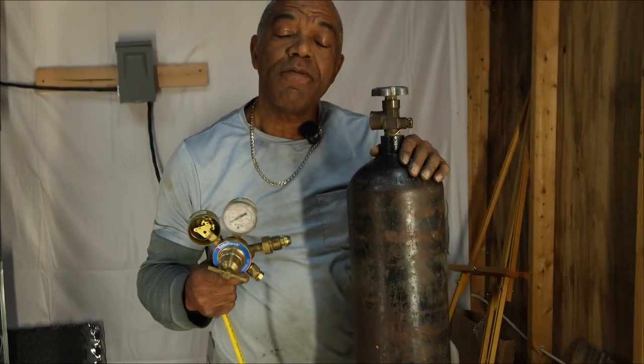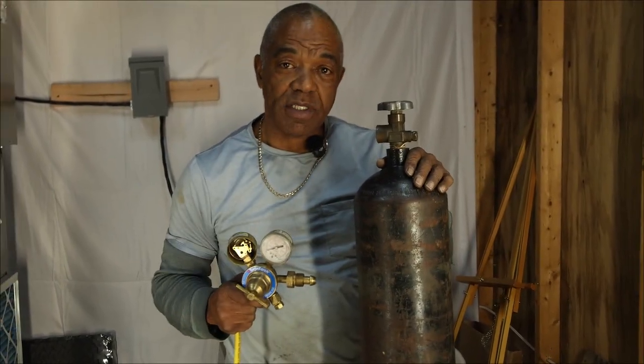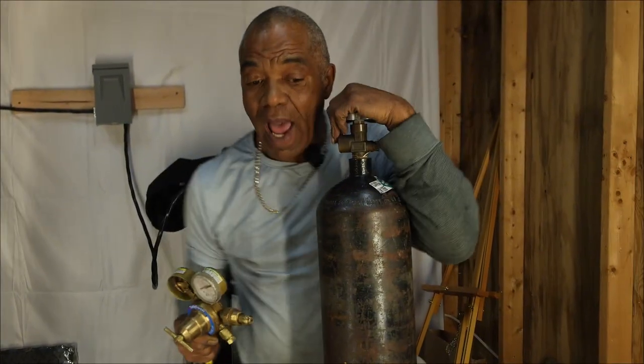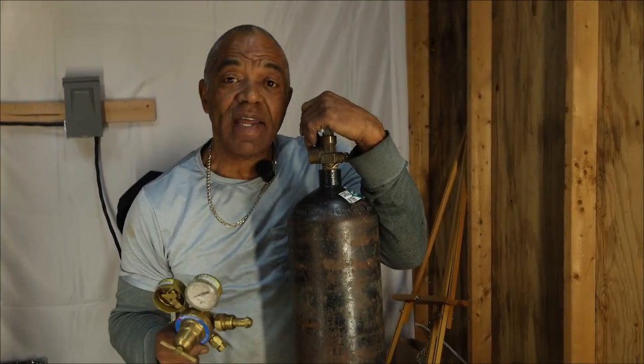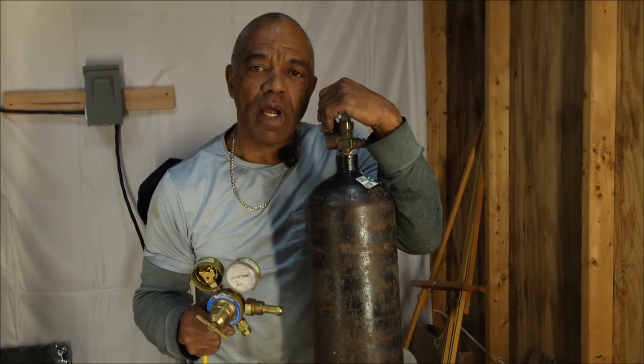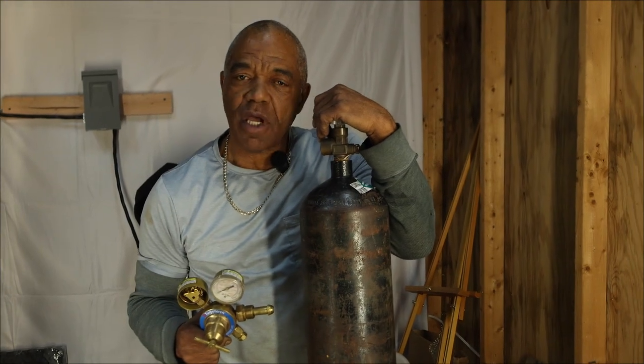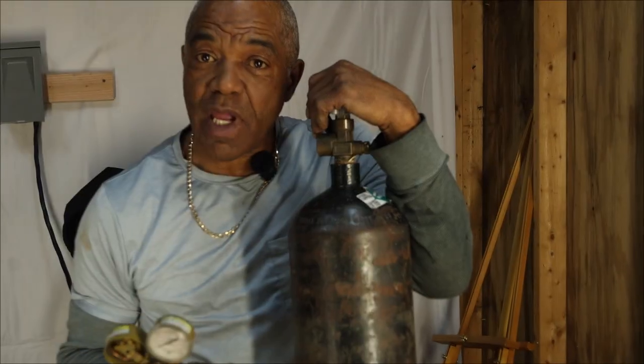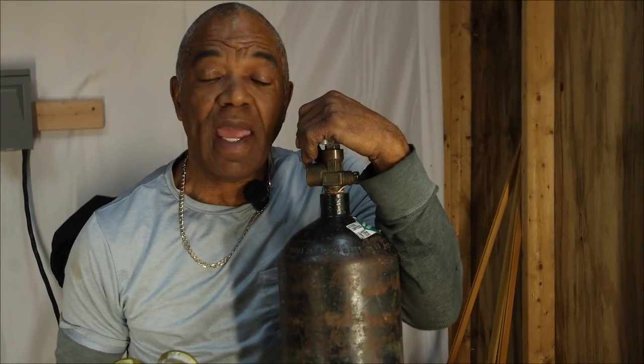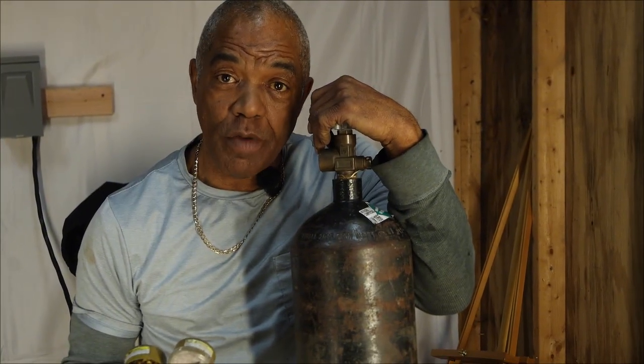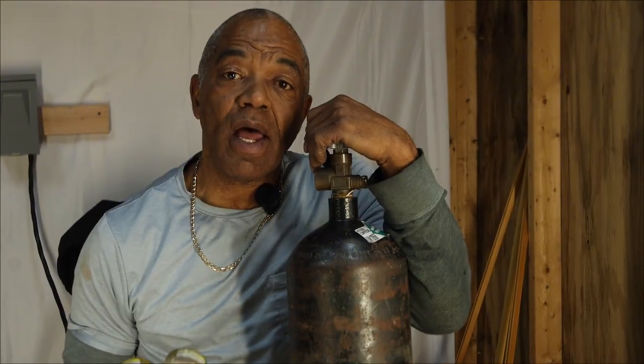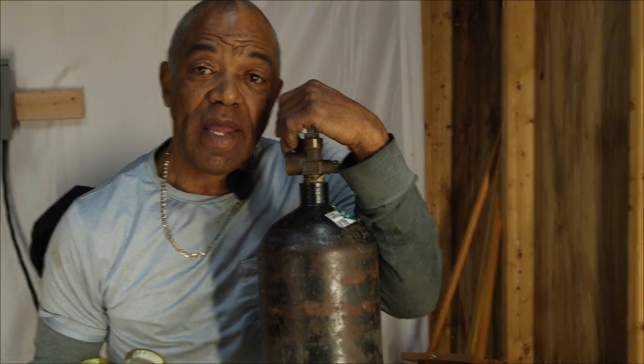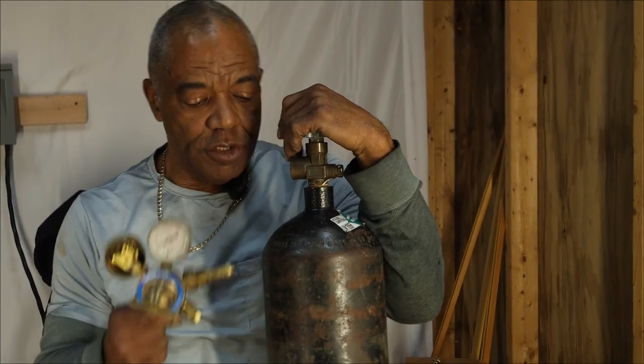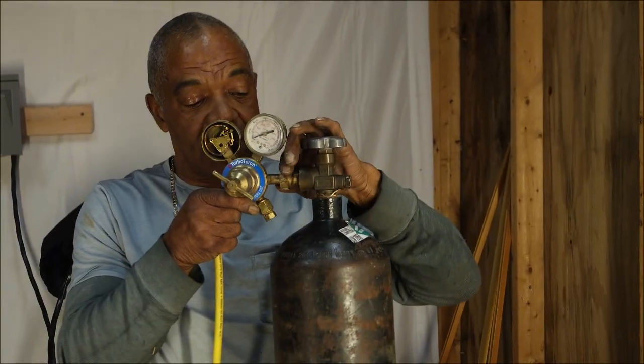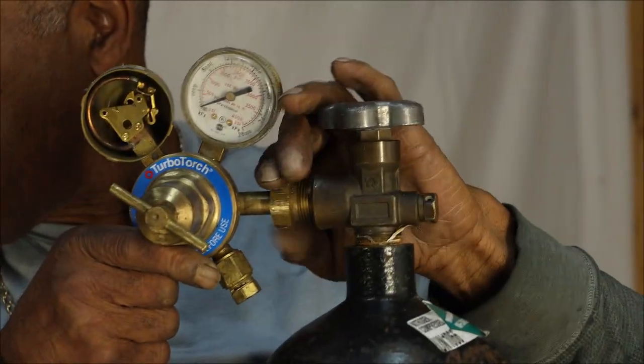I use it mostly for leak tests. If I come to your house and your system has no Freon in it, I am bound by law to find that leak and repair it before I put more Freon in, because the EPA says Freon is destroying the atmosphere and we can't release it anymore. So if your system is low on Freon, I cannot put new Freon in unless I find and repair that leak.